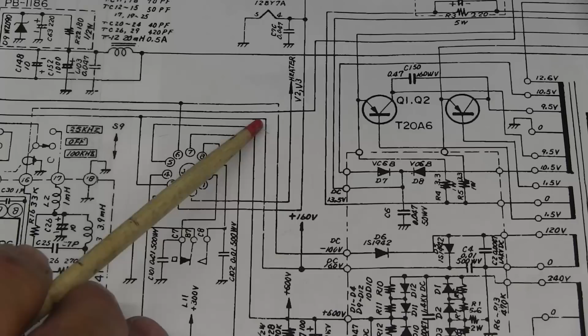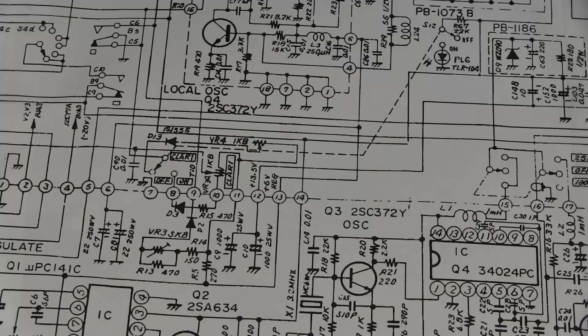So I think, again, if we go back to the 160 line, and we just come up and follow it, slide the schematic down. That line comes right on across, comes here, down to pin 6 of PB1547, and this is the regulator calibrator unit. So if we look at pin 6 and come down, the only thing there is two 22 microfarad at 250 volt capacitors in parallel.